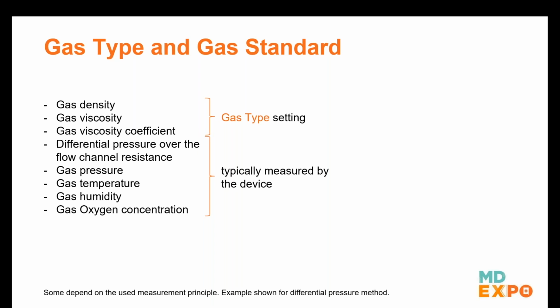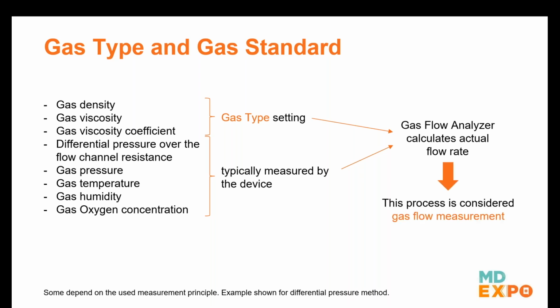The rest of these are things like pressure difference over the flow channel. Inside some analyzers that use a differential pressure to calculate flow, there will actually be a small pressure drop inside the channel. You can measure gas pressure, you can measure gas temperature, humidity, and oxygen concentration. Those are all done by the analyzer itself. And together with the gas type, it will calculate flow rates. And what's flow over time? Volume, right?